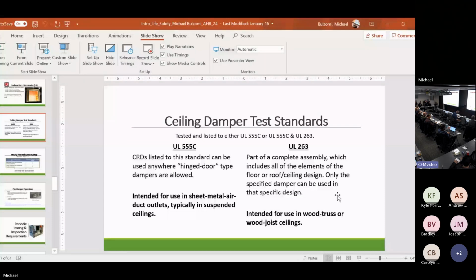But because of the nature of UL 263, that test, it's a full assembly fire resistance test. Everything in the room for L521 is the rating. It's not the damper. The damper has a UL label on it, but the damper on its own has no rating. The sheetrock, the trusses, the insulation, the bats, the blankets, the resilient channels, the damper, the boot, everything together is the rating because of 263. That's UL's perspective. Intertek does not believe the same thing. Intertek will test a damper and approve it for L521, L550, because they will make the logical argument: same construction, the damper passed in one, it's going to pass in all. Because Pottorf does not own L521 in the ETL directory, they own it in the UL directory.